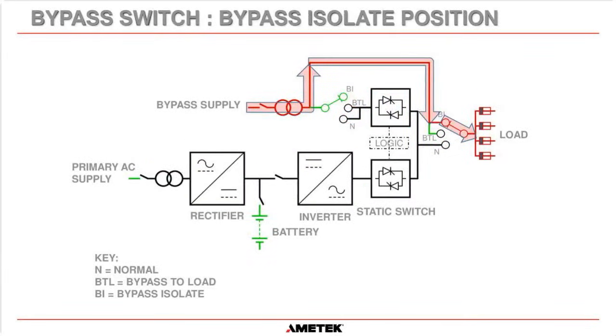It allows us, when I say us, I mean a service engineer from AMETEK Solidstate Controls, to test the system in the bypass to load position. Then the final position is bypass isolate. What that does is we move to this top position here, and then we move to this top position here.